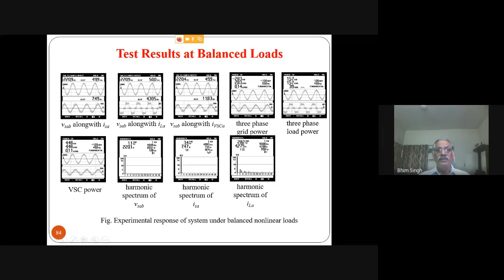And this is the case when you have an unbalanced load. I mean, you have a single-phase load connected line to line. You don't have a load in the third phase, but the grid currents are balanced. So apart from harmonic elimination, it is also doing the load balancing on the grid side. You have a balanced load, so the inverter is taking care of it.